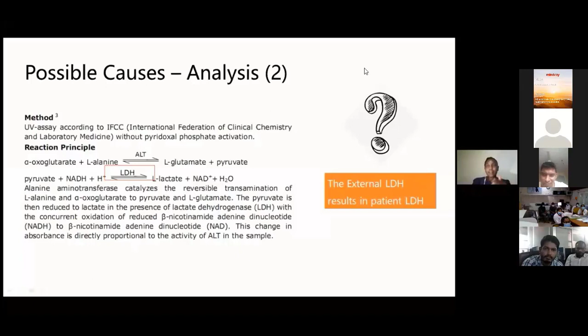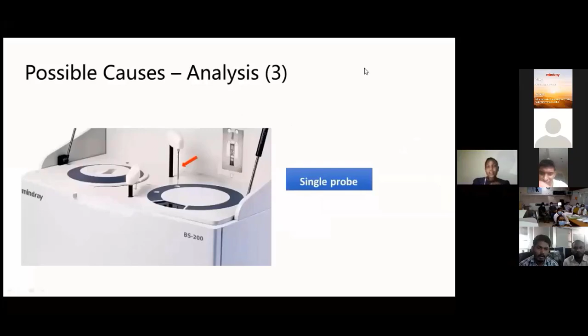So we went further and checked, you can see in that picture, the analysis 3. Physically, the hardware part of it, the probe is okay as shown by the arrow. That's the sample reagent probe. You can see the mixer in the washing station. So in terms of carrying over, everything is okay. Now, we got to seek further support. It doesn't end with you.